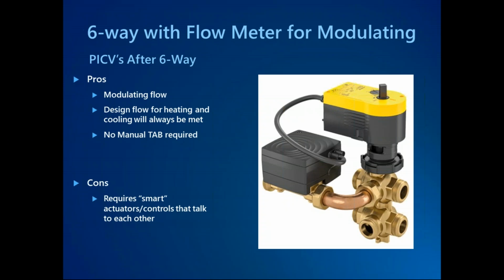solution. But again, you have a flow sensor that's talking back to your smart actuator on the 6-way in this case, telling it what GPM it's actually seeing, and the 6-way actuator knows, is it heating or is it cooling? Do I need to modulate up or down a little bit? And this solution can remove any additional balancing valves.